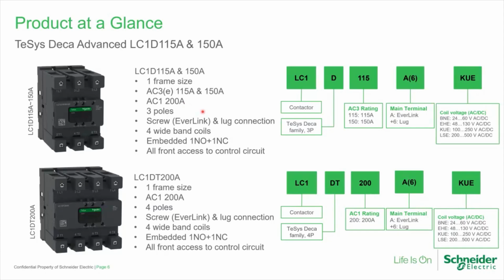Let us talk about 115 ampere and 150 ampere. As I mentioned, the existing contactors of 115 and 150 ampere were tested for AC3 duty, whereas this new range is tested for AC3e duty. When we say AC3e, these are suitable for IE3 motors and IE4 motors, which are more prevalent in today's time. Similarly, these contactors are rated for AC1 duty as well for 200 ampere.